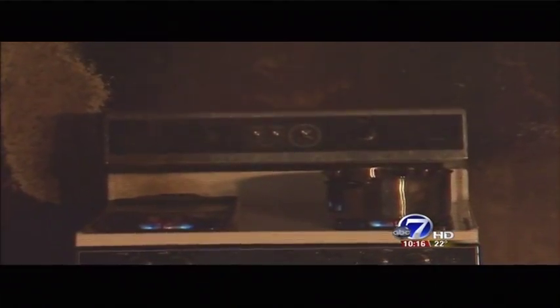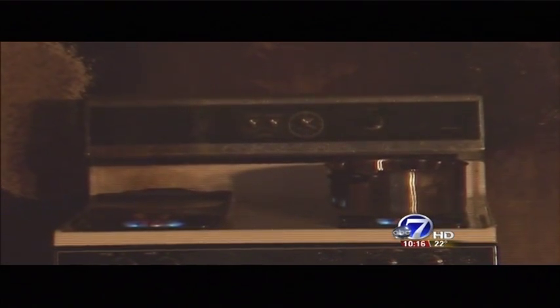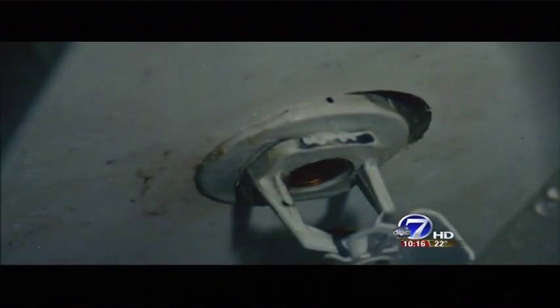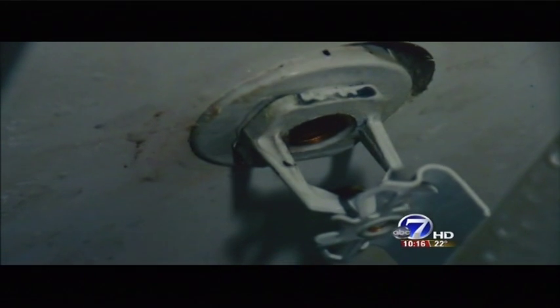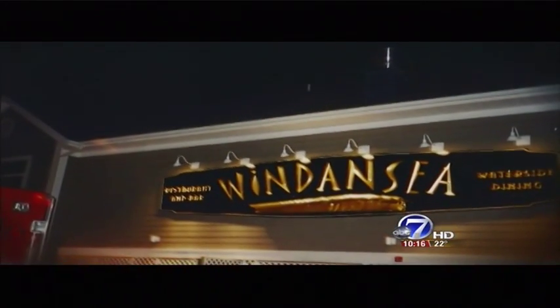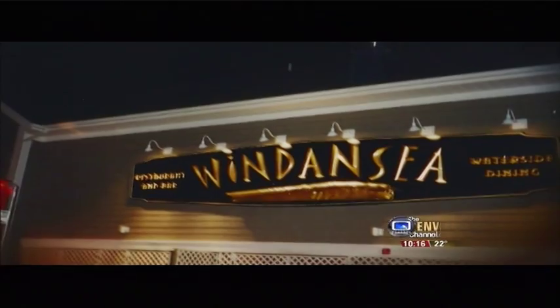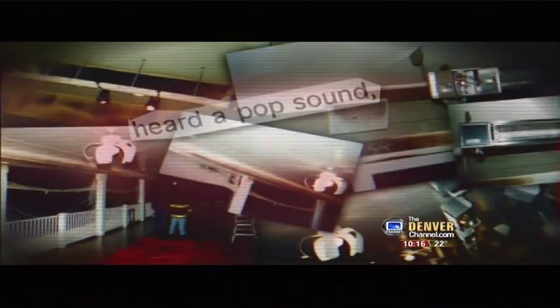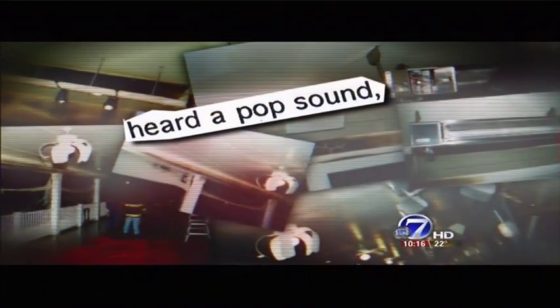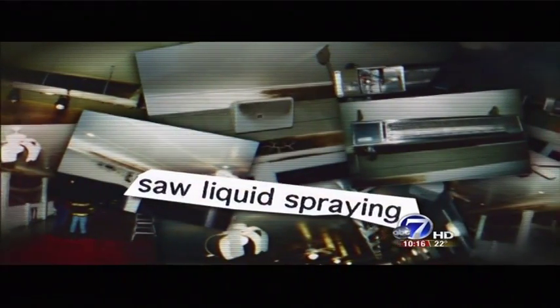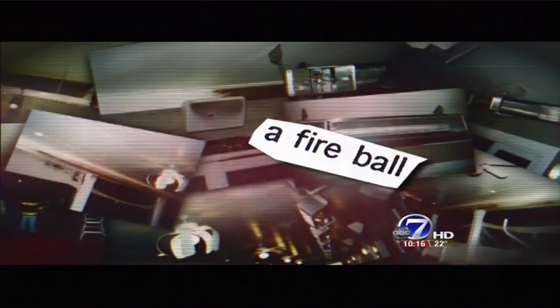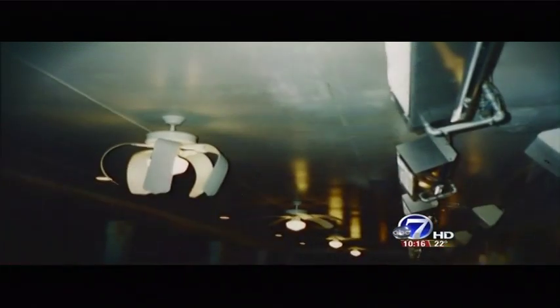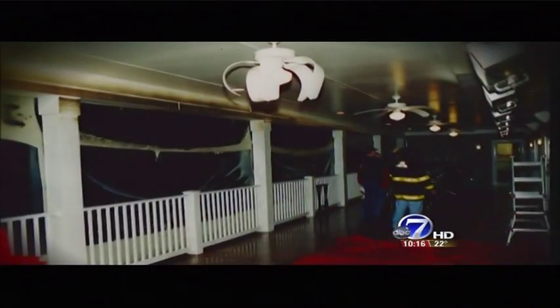That is important because our research found another fire involving a sprinkler system, this one charged with propylene glycol antifreeze, on October 28, 2001 at a restaurant in Highlands, New Jersey. 19 people were hurt as witnesses reported hearing a pop sound, then saw liquid spraying down from above, followed by a fireball developing at the ceiling. That blast melted the ceiling fans and blew out windows.